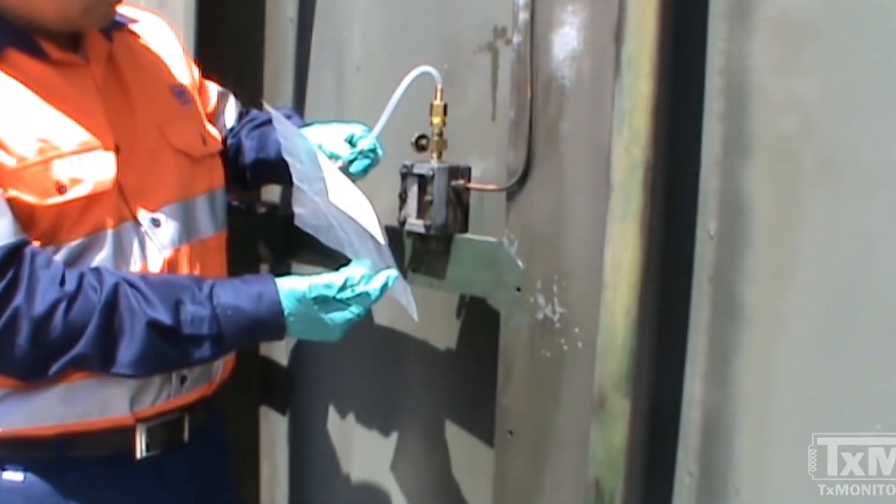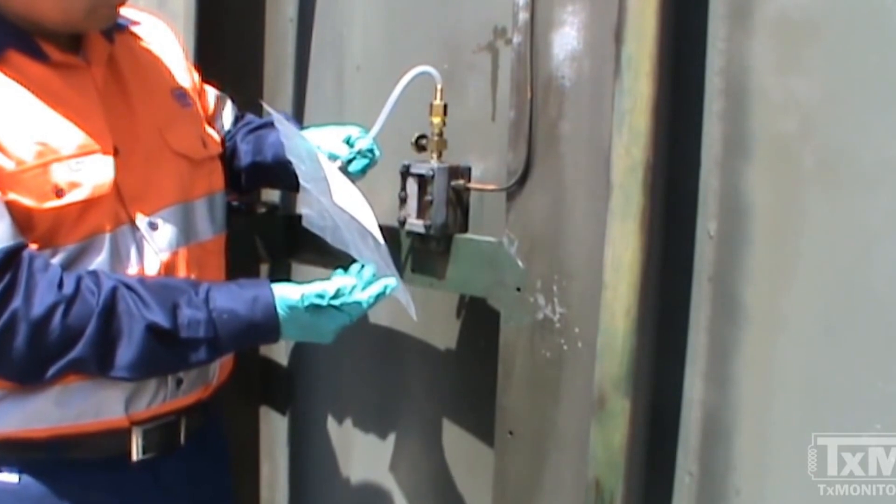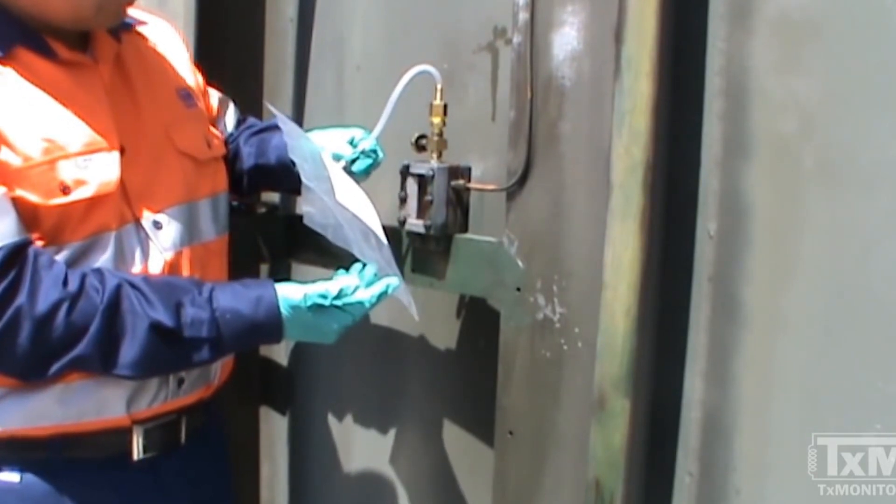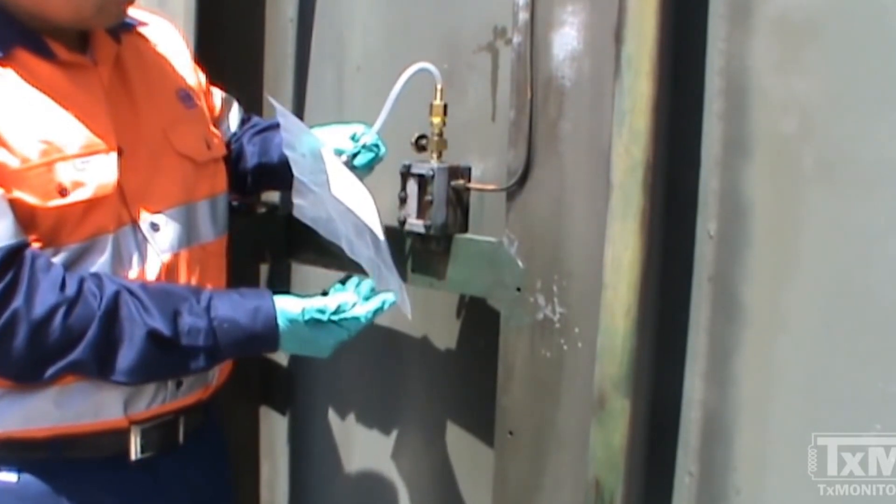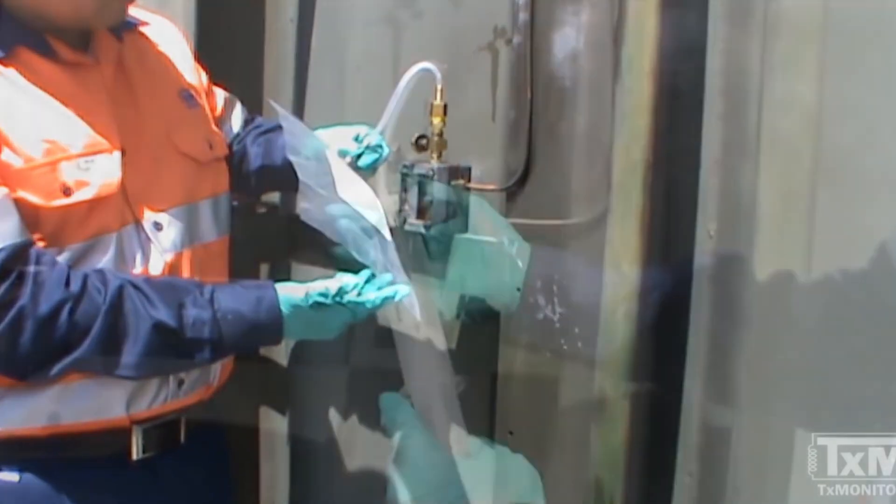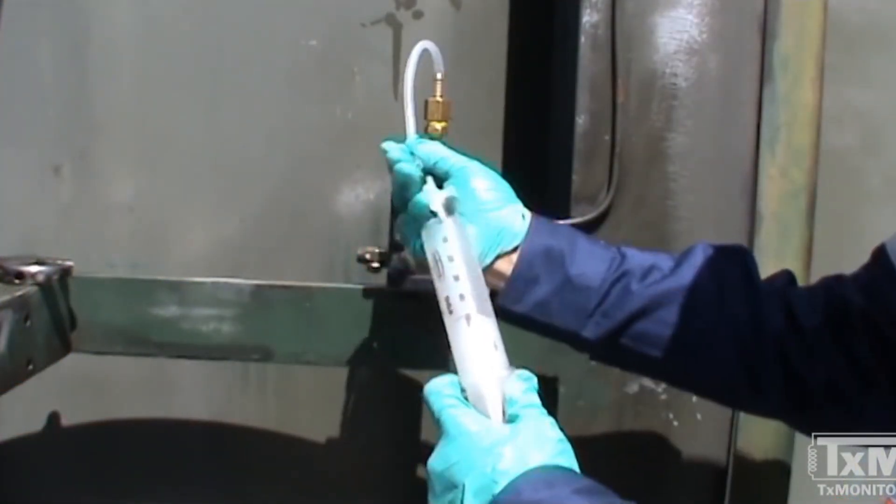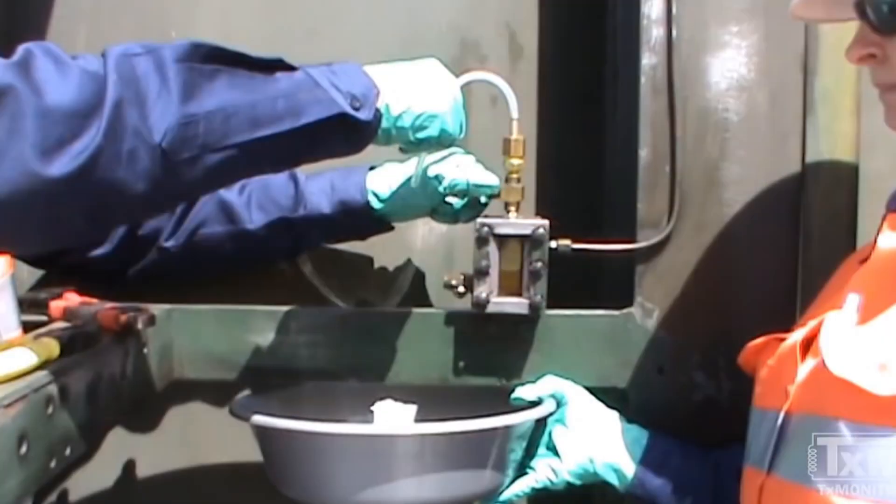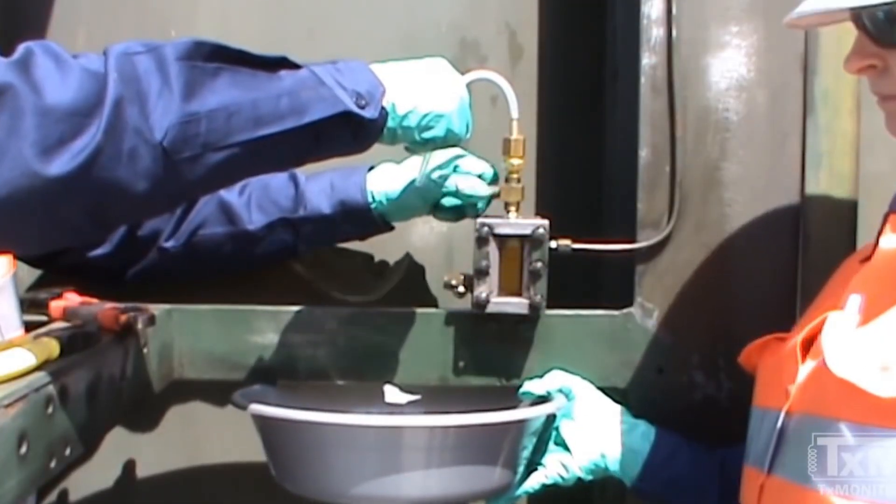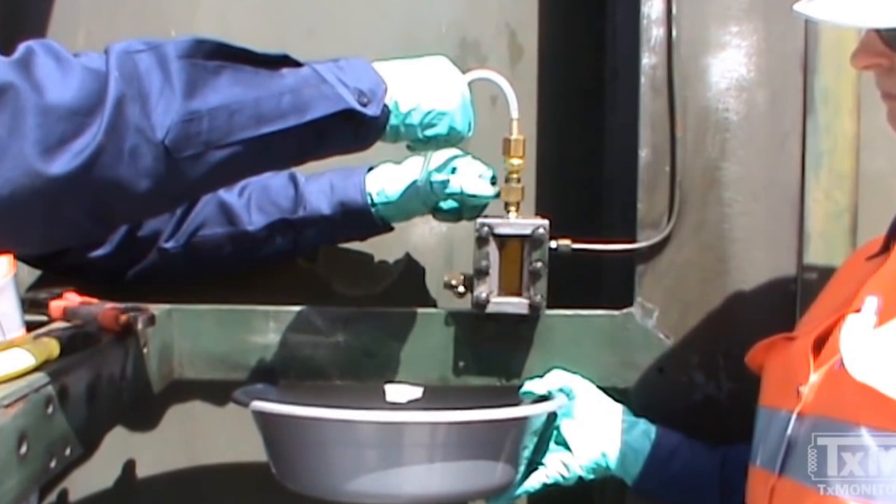Use additional syringes or bags if necessary to collect all the gas accumulated in the Buchholz relay. When all the gas has been retrieved, ensure that the gas sampling device is purged by opening up the top port until oil pours out.